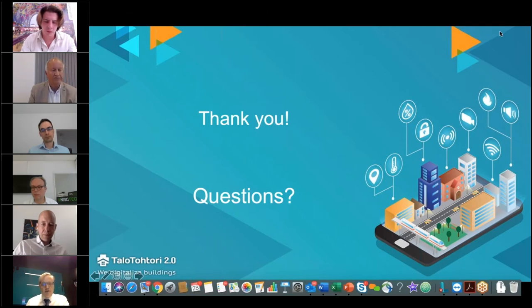Yeah, that's a good question. And in fact, we have another project starting where we have been discussing how to scale this up, really. And there is really a potential. One of the downsides of this particular case is that the heat pump temperature that it can produce is not high enough, which typically is required by the Finnish district heating network. And that is probably the only major blocking issue for scaling up.